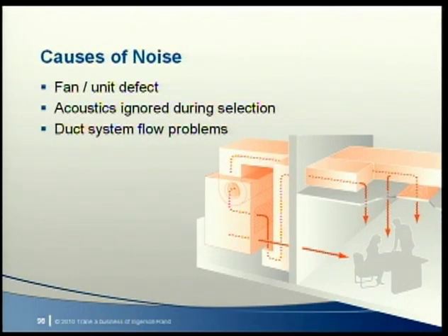Checking for a unit problem is a good first step. These problems can typically be resolved quickly. I rarely see problems with a defective fan, but I have seen cases where something simple, like an overlooked shipping restraint, was causing a problem.